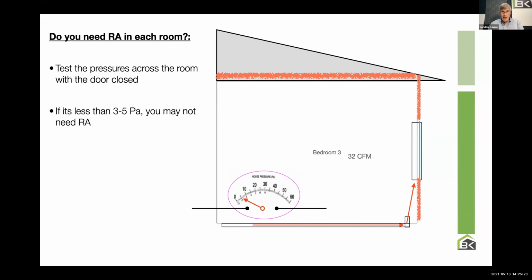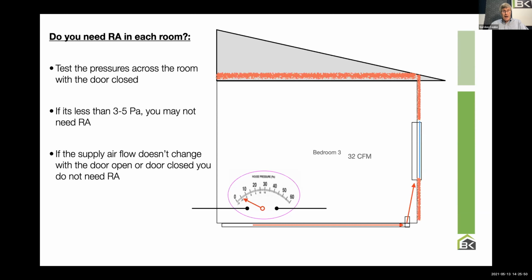Return air is simply a pathway for the air that you put into the room to get out of the room. That's all it is. So all I need to know is, did the pressure change in the room? And if it did, then I need return air. I just did this at a house. They'd been arguing for years, well, a year and a half. Need to put in return air, need to put in return air. They're worried about privacy issues and noise. They didn't want to put it in. I went out to the house, I measured the pressure, it didn't change. The airflow didn't change when I opened the door or closed the door. So return air is not going to help. If the supply flow doesn't change with the door open or door closed, return air is not going to help you in that room.